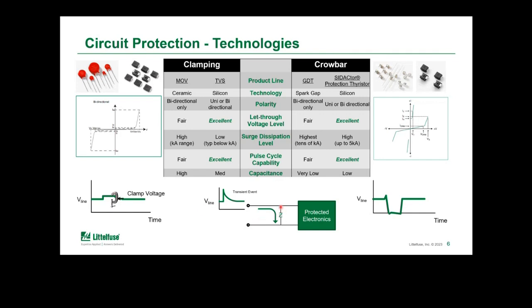So a suppressor is typically placed across the line, and then during a transient event, it will change its resistive characteristics and begin to conduct current and redirect it away from the protected circuit or protected electronics, basically mitigating the amount of energy that comes from the transient that would actually reach the electronics. And there's 2 basic types of suppressors in the industry. The first one is called a clamping device. Now, a clamping device, when a transient occurs, will essentially chop off the top portion of this transient event, and that energy will be absorbed within the suppressor.